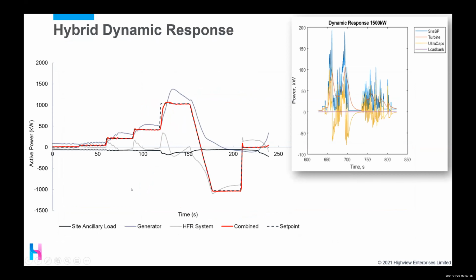These graphs further illustrate the same point. In the left graph, we're following a set point, the black dotted line, and we have the generator response, which is the dark gray line here, following the load as best it can. The black dark line is the site ancillaries, so this minus this is the net output onto the grid. Finally, we have the light gray, which is the hybrid frequency response system. The ultracaps, the flywheels, and the load bank are taking up the slack to allow this response, the red line, to follow the dotted line insofar as possible. This is an actual trend and it follows it quite closely.